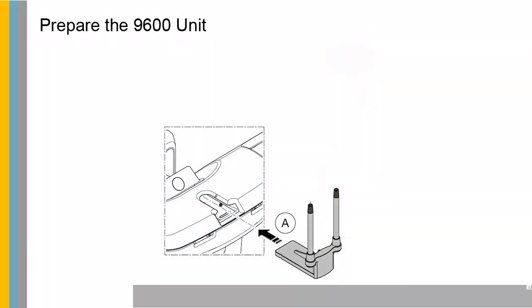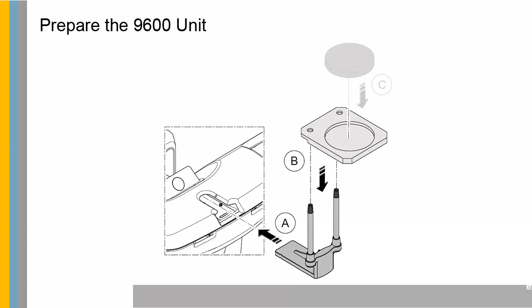To prepare the unit for acquisition, first insert the 3D bite block support into the chin rest base. Then place the dental impression holder on the 3D bite block support. Next, place the black foam on the dental impression holder.